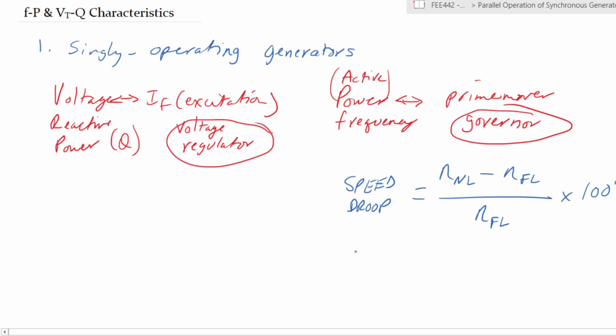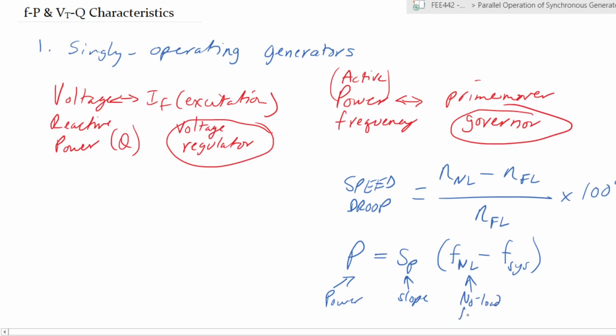Okay, so in the case of power, you will have power is equal to SP times the no load frequency minus the frequency of the system, whereby the power is the active power or generator output. SP is the slope of a characteristic we will see shortly. This is your no load frequency of the generator at that particular set of generator settings, and you have the system frequency, the frequency of the system that you are supplying.